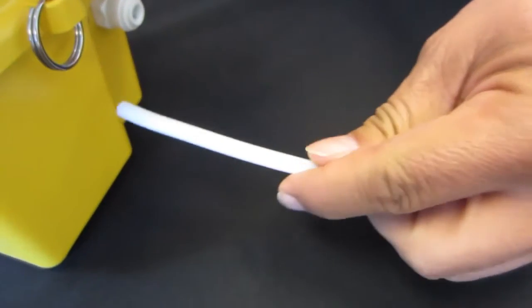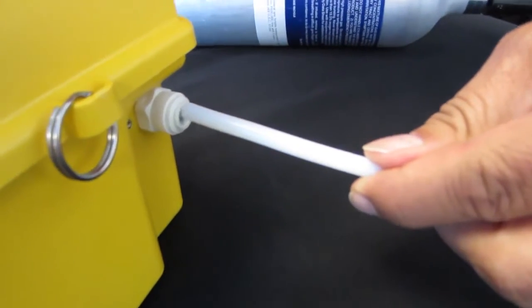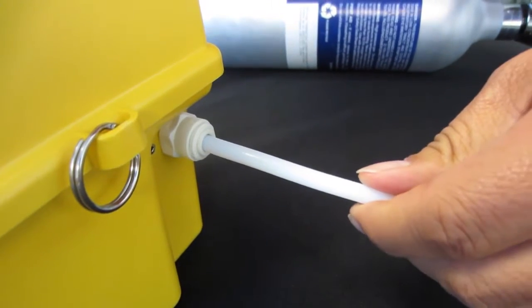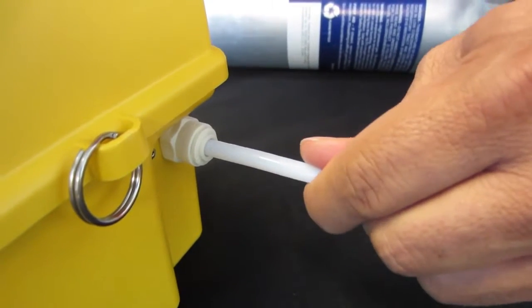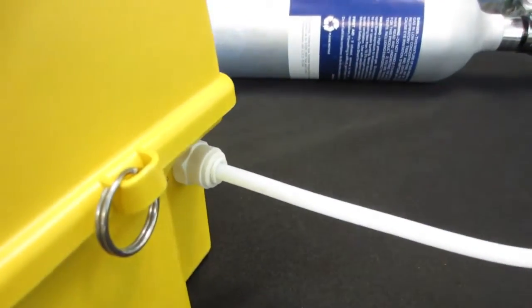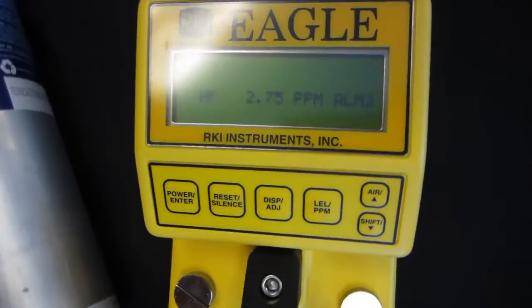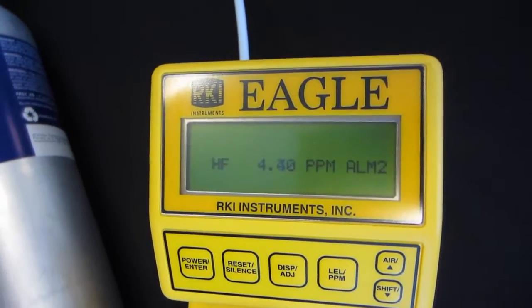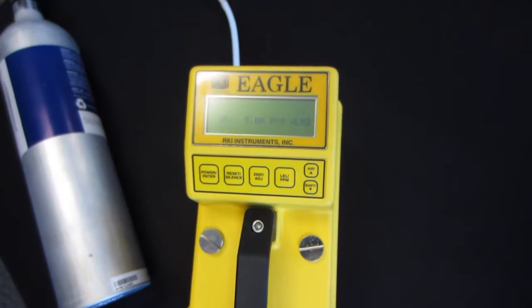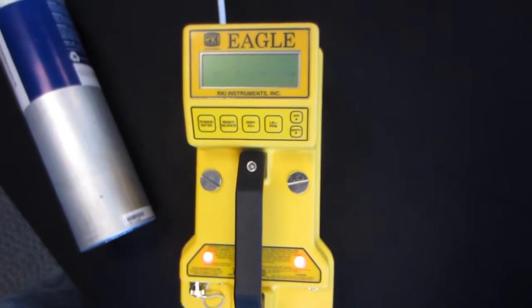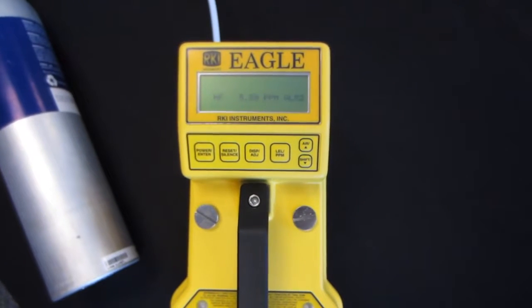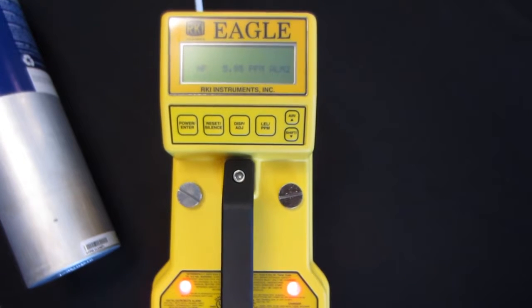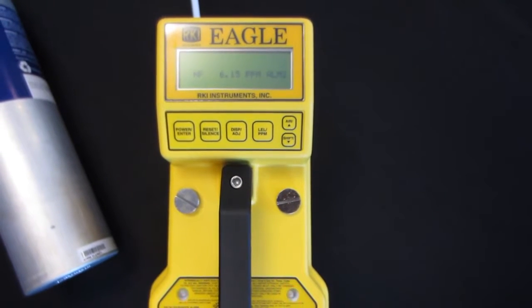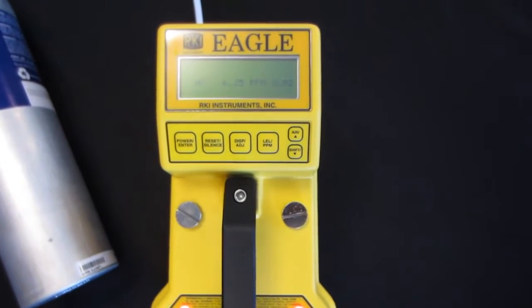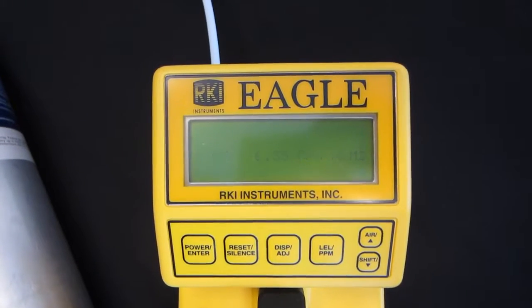Okay, so now we'll attach it. We're going to take this piece of Teflon tubing and just firmly insert it into this push fitting on the Eagle and push firmly until you feel it seat. You can also hear it sometimes seat as well. Okay, so now the Eagle is climbing, and you want to apply gas for at least a minute, maybe a minute and a half. When we calibrate the unit, we apply the gas for 2 minutes and then make the adjustment at the 2-minute mark. But right now we're going to just apply the gas. I've had it going for about 30 seconds now. And we'll see how close it gets to 8 parts per million.